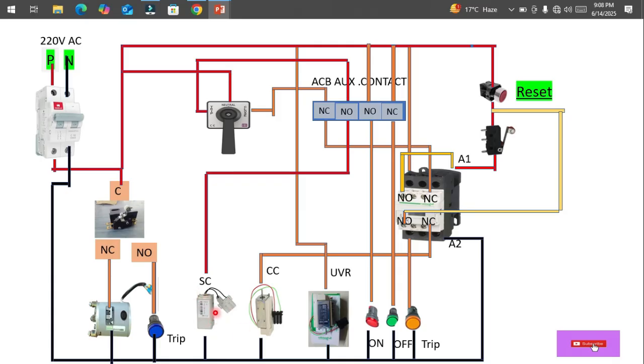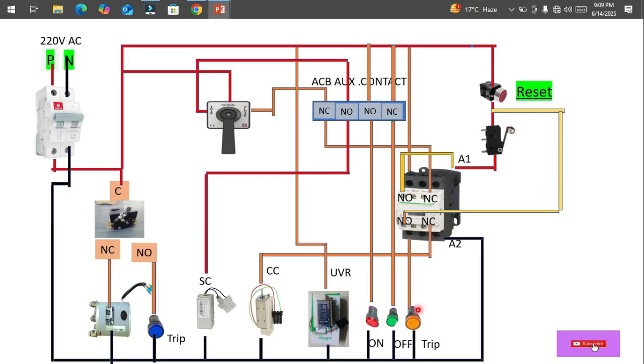Next is the shunt coil (SC), which is for tripping — for tripping the ACB. This is the closing coil, which is used to close or make the circuit. This is the under-voltage relay: in case any phase or voltage is absent, this will trip the ACB. Finally, these are the indicators for monitoring the air circuit breaker — red for on, green for off, and yellow for trip. These are the major components of the ACB.